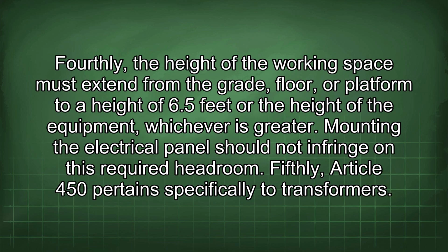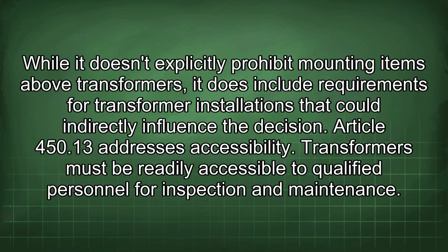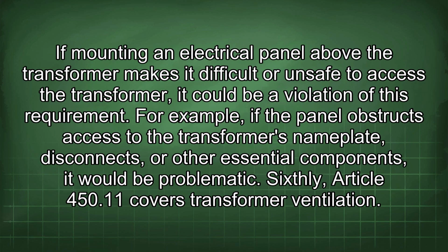Fourthly, the height of the working space must extend from the grade, floor, or platform to a height of 6.5 feet or the height of the equipment, whichever is greater. Mounting the electrical panel should not infringe on this required headroom. Fifthly, Article 450 pertains specifically to transformers. While it doesn't explicitly prohibit mounting items above transformers, it does include requirements for transformer installations that could indirectly influence the decision. Article 450.13 addresses accessibility. Transformers must be readily accessible to qualified personnel for inspection and maintenance. If mounting an electrical panel above the transformer makes it difficult or unsafe to access the transformer, it could be a violation of this requirement.